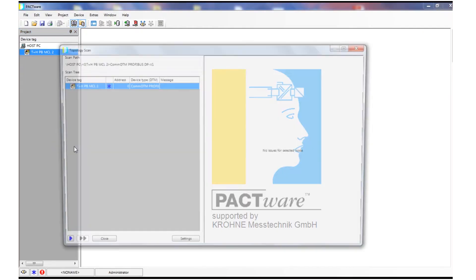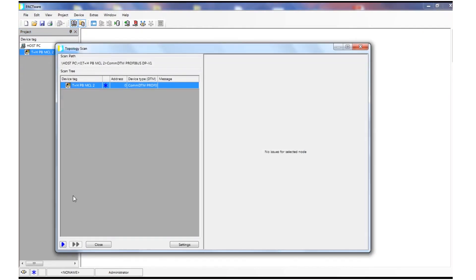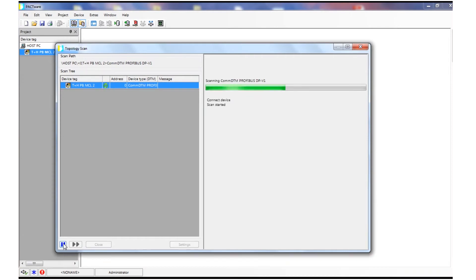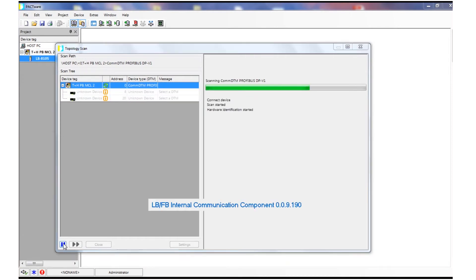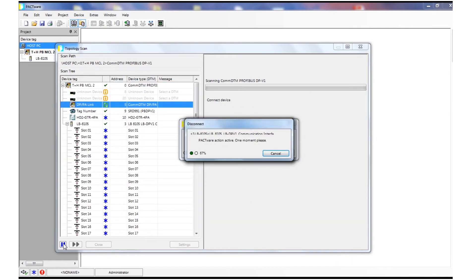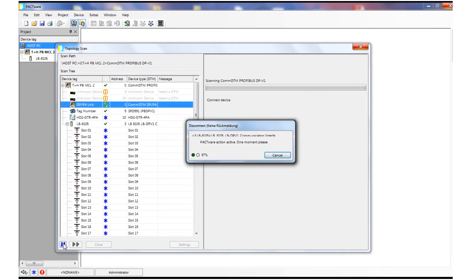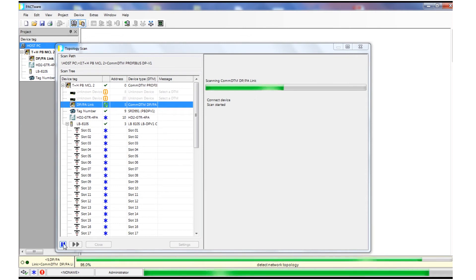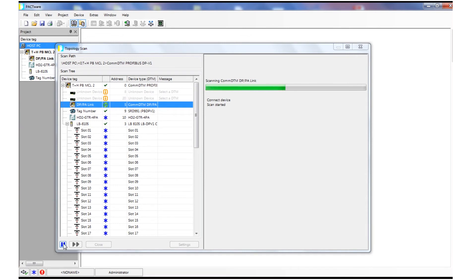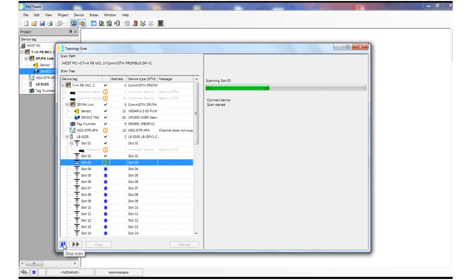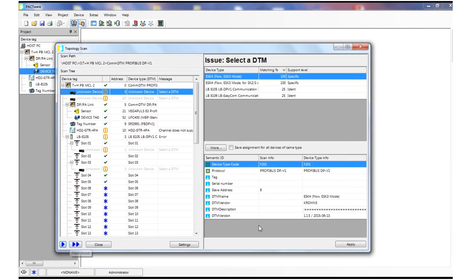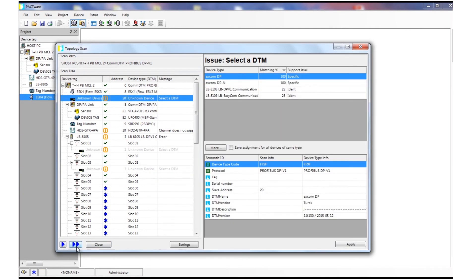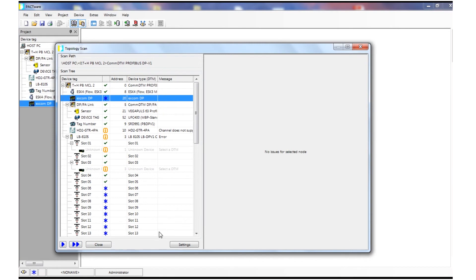Now we can use Pactware's topology scan again. The add-in takes care for all the rest of the setup. It finds its way through all the networks and adds all the necessary DTMs to the project: the network DTM provides access to the Profibus DP network via Ethernet, the gateway DTM for the transition from Profibus DP to Profibus PA, and finally the device DTM for our Profibus PA instrument.